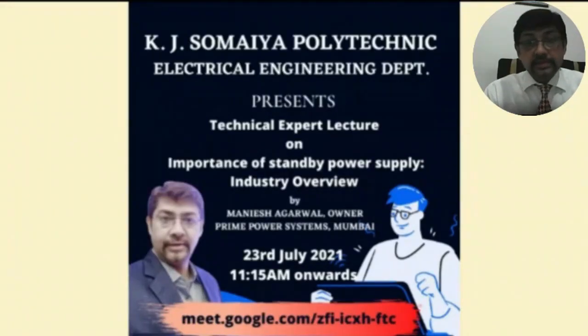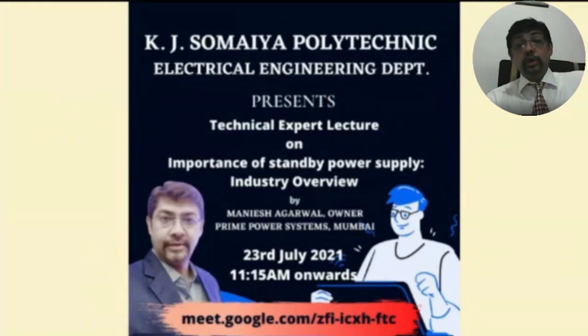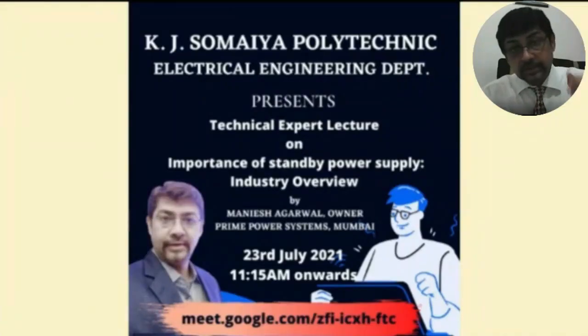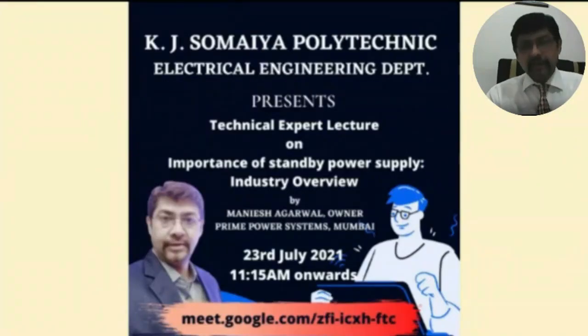Now, Tesla is coming, but cost-wise it is very, very high. At the same time, it is a battery backup, so again it has a constraint that it cannot run for a longer period. Suppose you have a bungalow and you want a UPS system there for 4, 5, 6 hours, then any battery backup system is going to be sufficient.